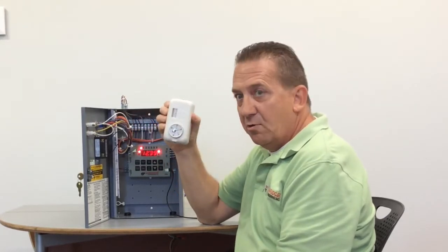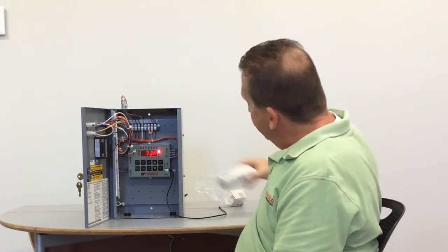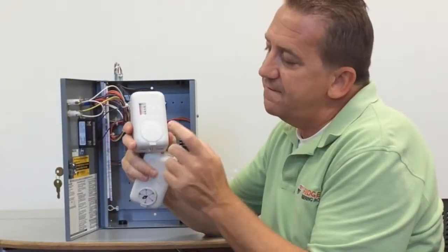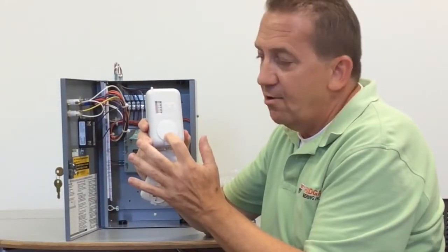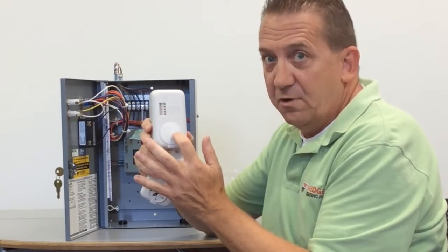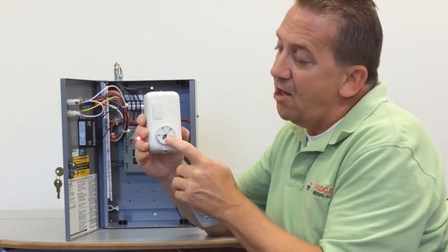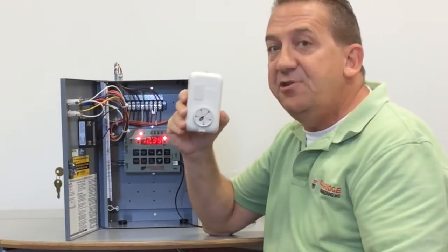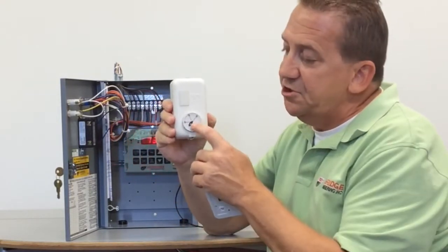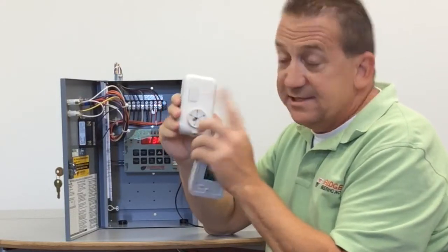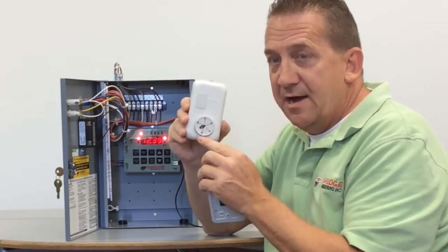This must be mounted outside the panel in order to sense the space temperature just like the original T-244A. This was one component only. Remember the tamper-proof is two components. On the one control you have a thermometer and no dial, and this is your TS-244A, which S stands for sensor. On the other control you have a dial and no thermometer. This is a TD-244A. This is what is used to set your desired space temperature in your occupied mode.